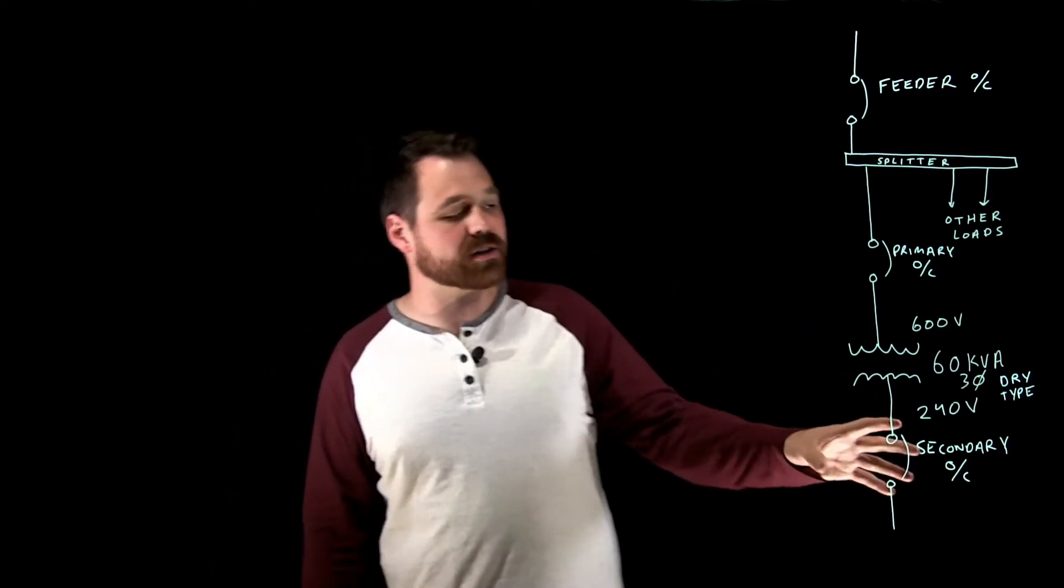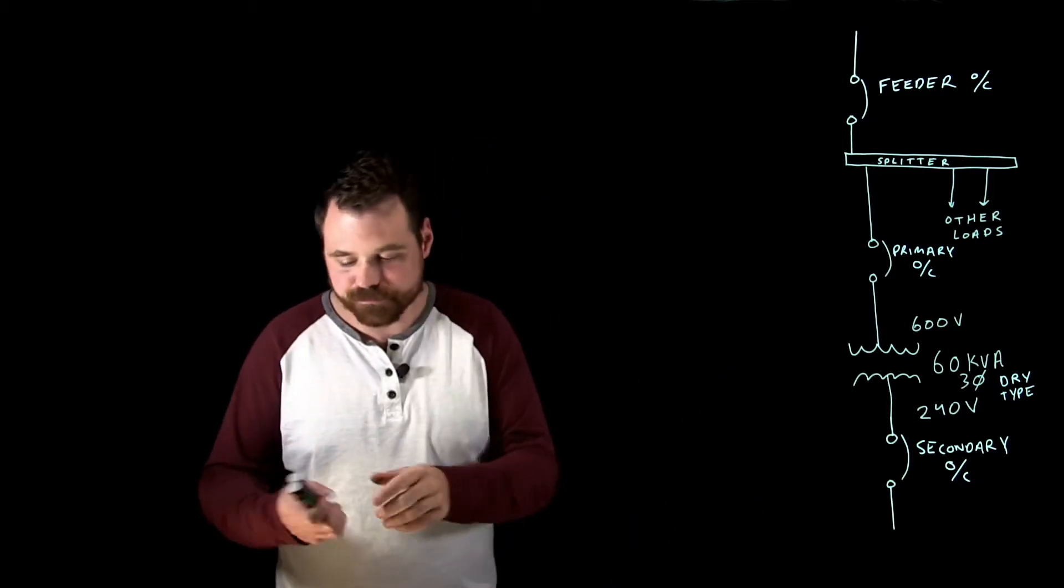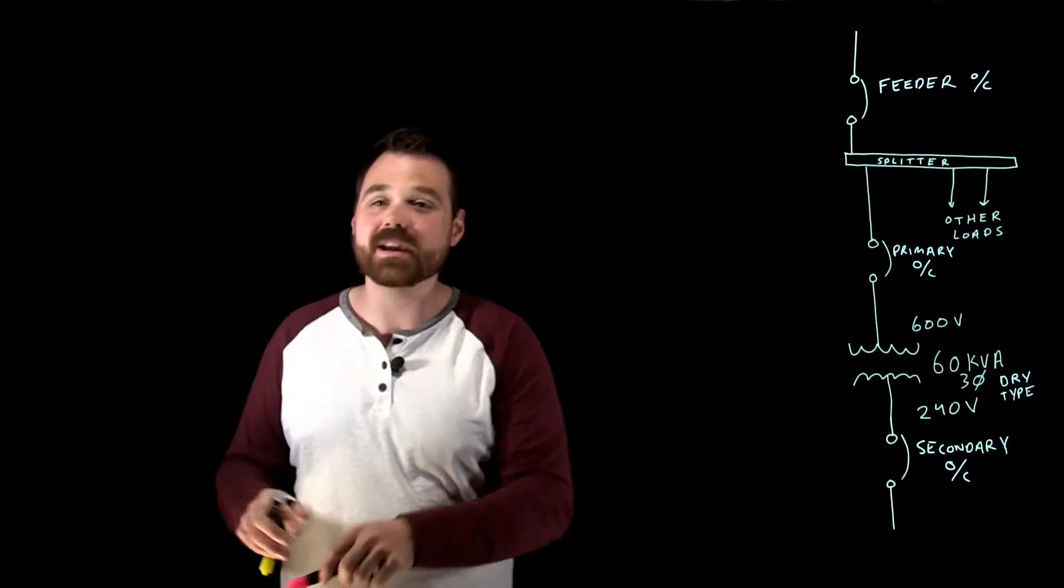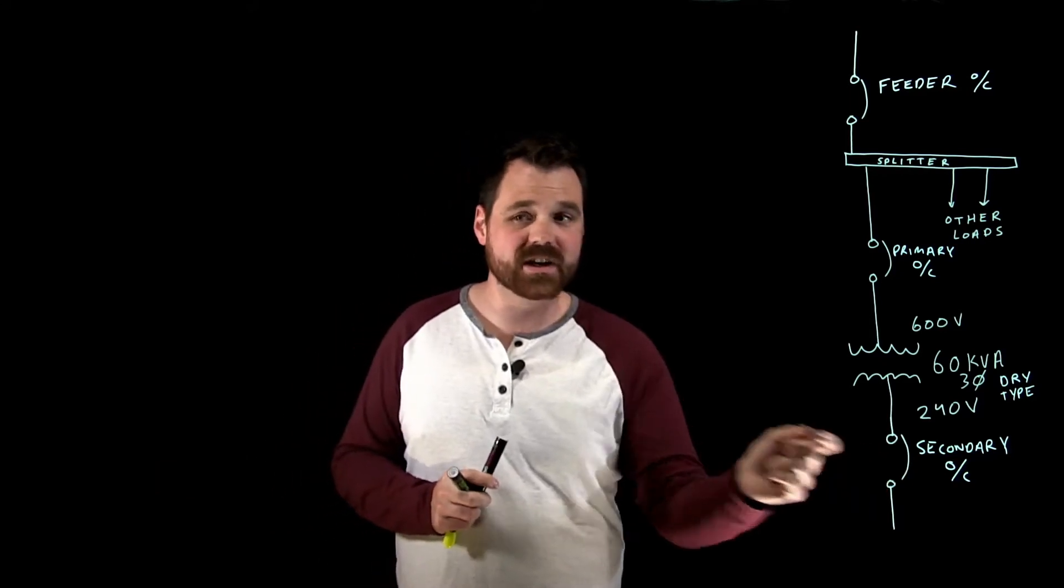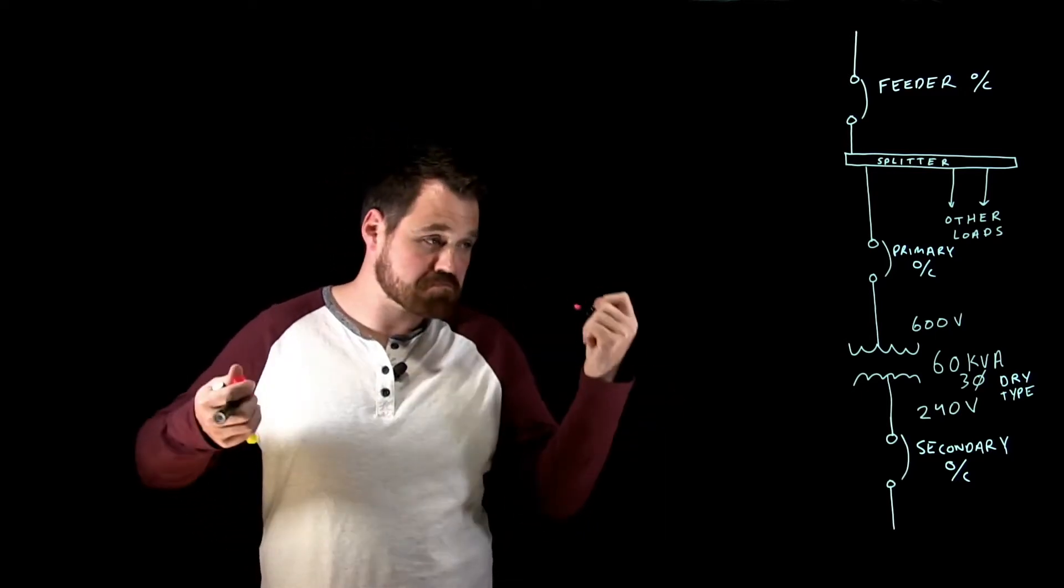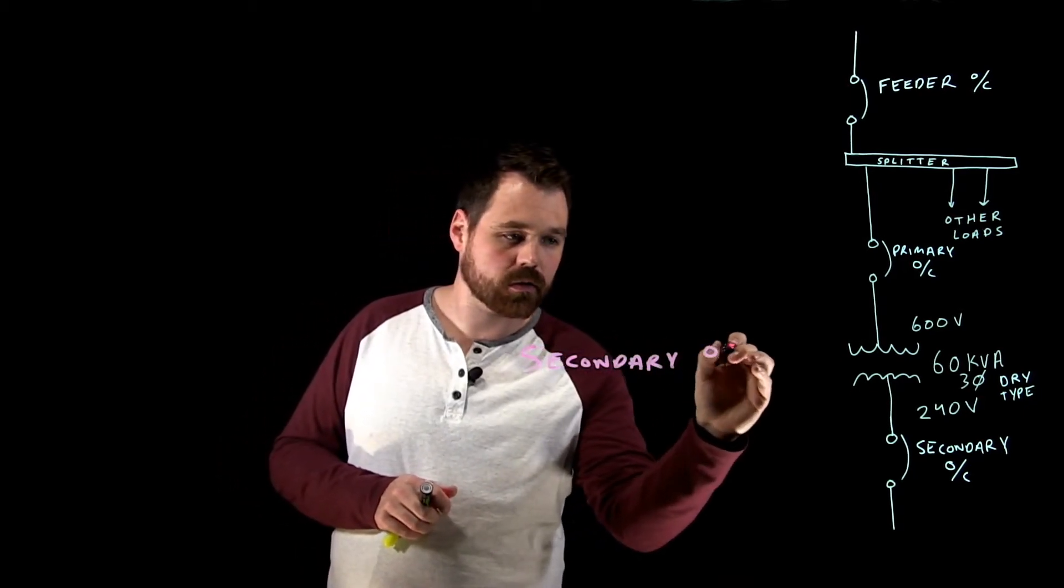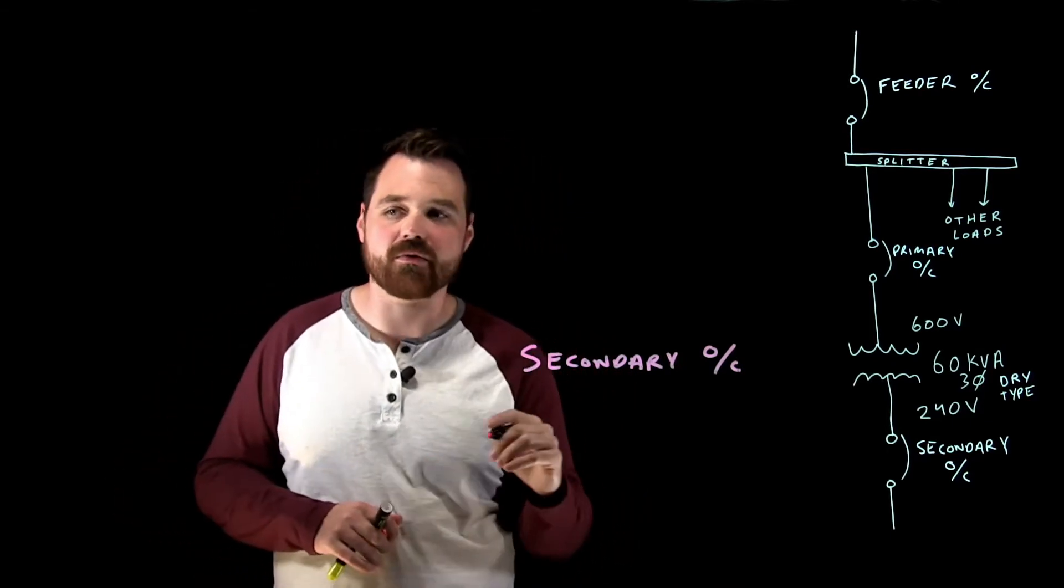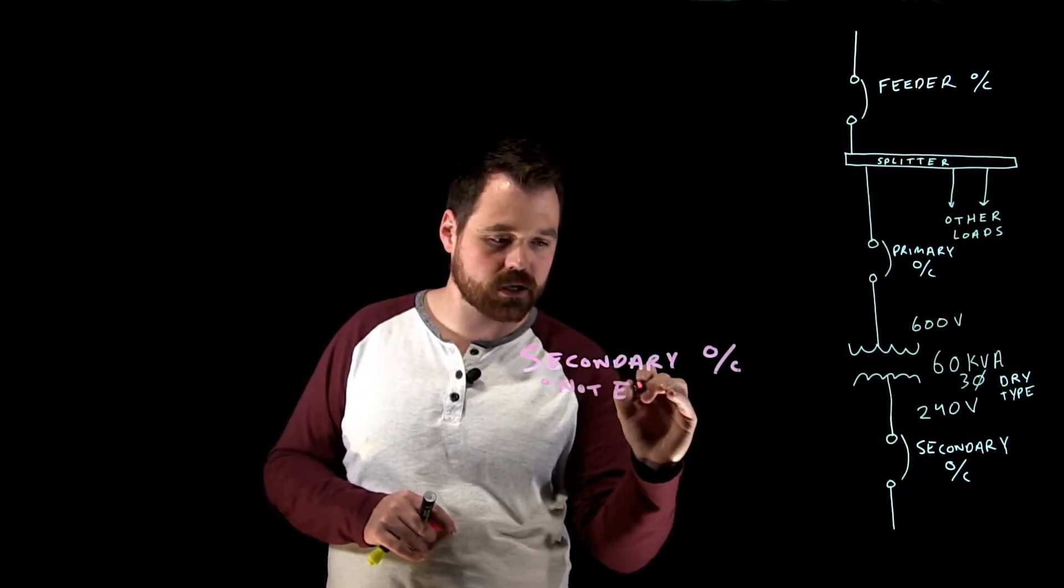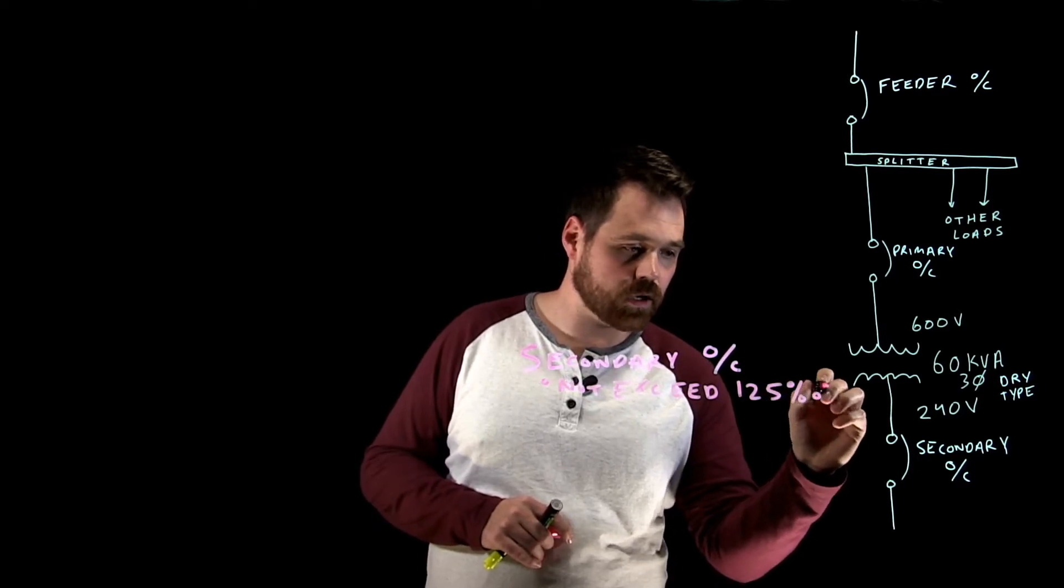Let's say we are installing a secondary OC. Our rule tells us okay, if you're gonna install a secondary overcurrent device it shall be installed and sized so that the overcurrent device does not exceed 125 percent the rated current of the transformer. So if we're installing a secondary OC, and this is a big if, it tells us that you cannot exceed 125 percent of your rated secondary current.